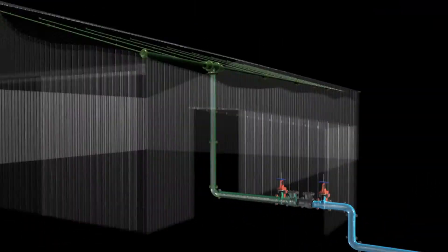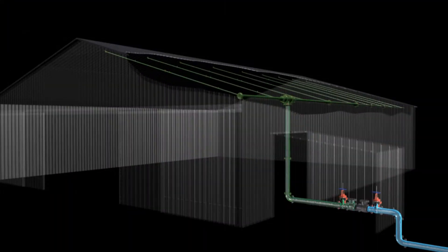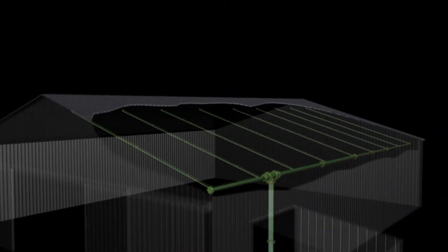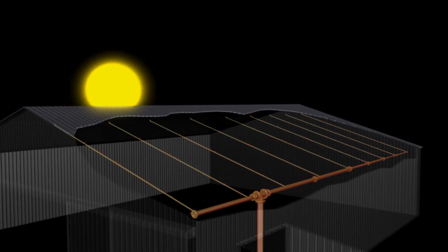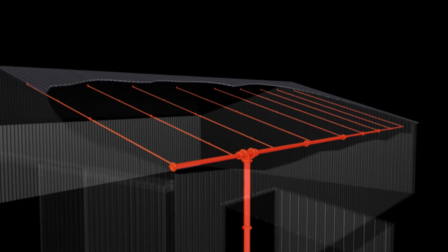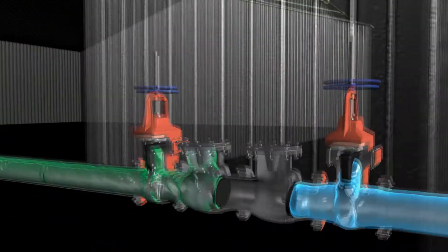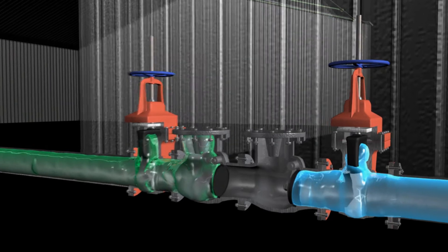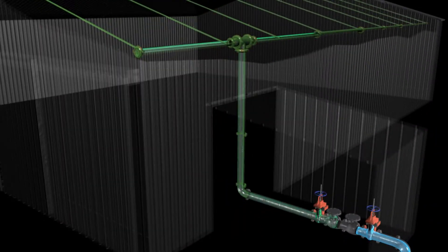When temperatures increase in the building during the day, the anti-freeze in the piping is subject to thermal expansion, causing unwanted pressure buildup up to the backflow preventers. This high pressure can cause failure in weakened areas of the piping.